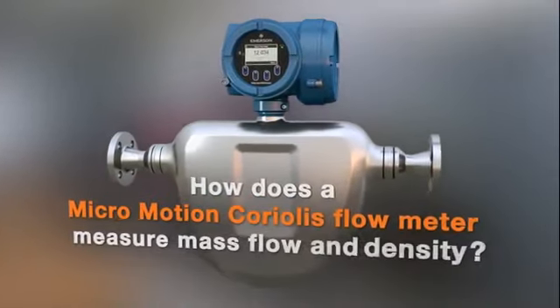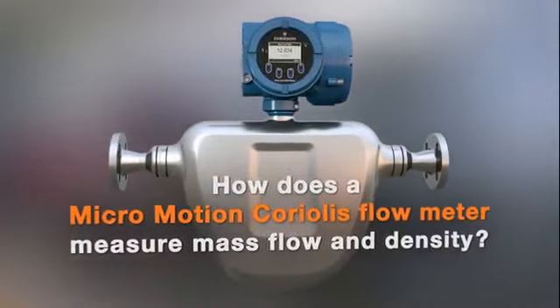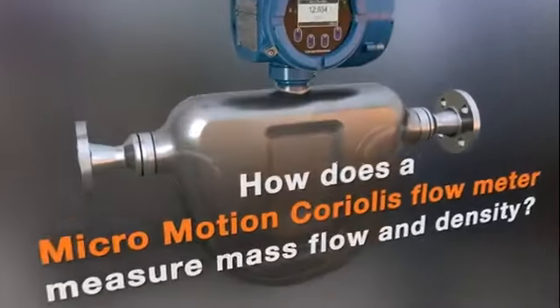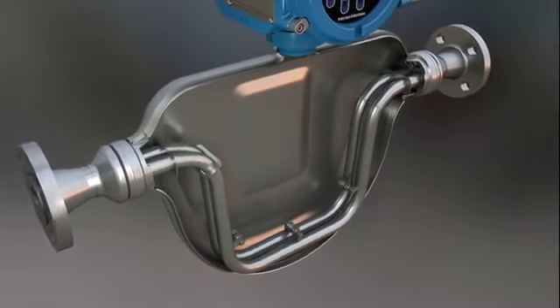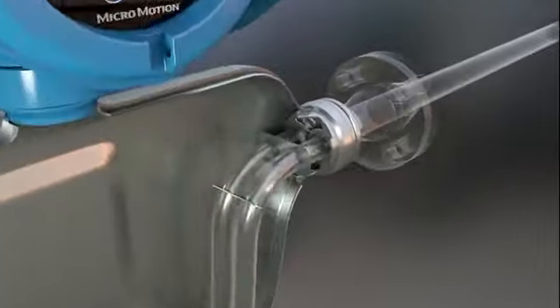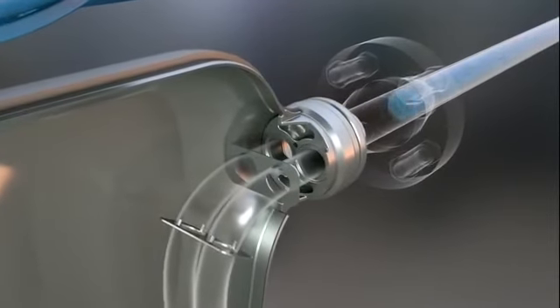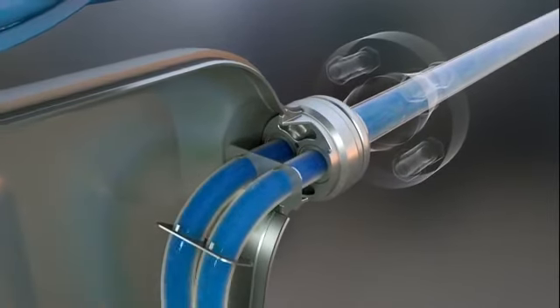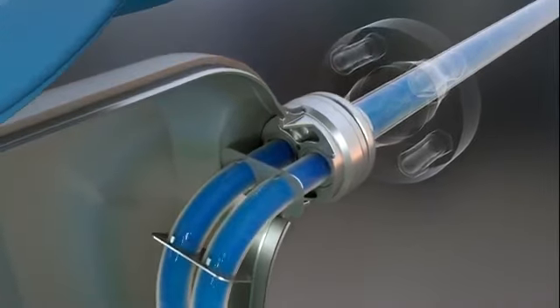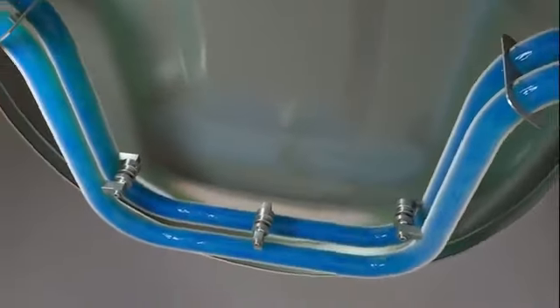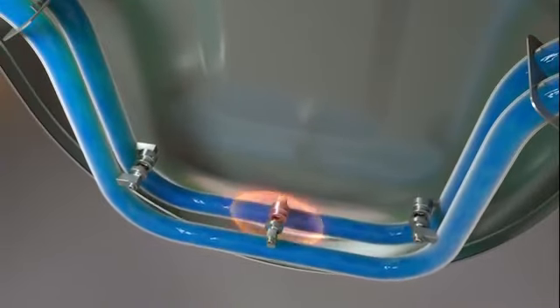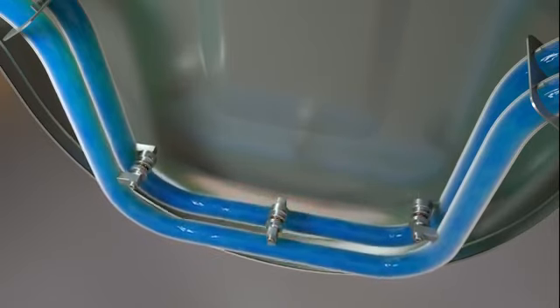How does a Micro Motion Coriolis flowmeter measure mass flow and density? The flowmeter has dual parallel flow tubes. When the process fluid enters the sensor, it is split. Half of the fluid passes through each tube.